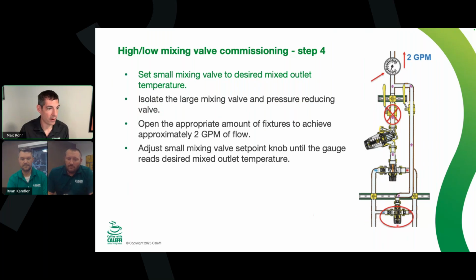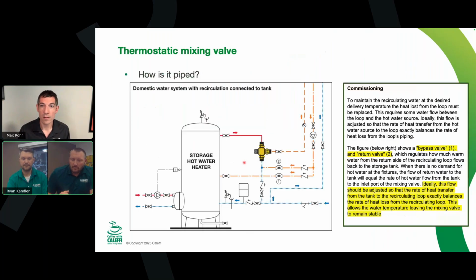Yep. The key here is that we want the small mixing valve to do all the work until there's too much flow going through it. In PRV terms, the pressure falls off, we're not keeping up from a pressure standpoint. Then the PRV notices the downstream pressure is low, just like the cold inlet into your house, and says, okay, the pressure is low, I'm going to open up a little bit, and that engages the bigger valve. That technically works great. The tricky part is being able to find steady 2 GPM flow and steady 14 GPM flow to do this, and that's why pre-occupancy is always the best case scenario.